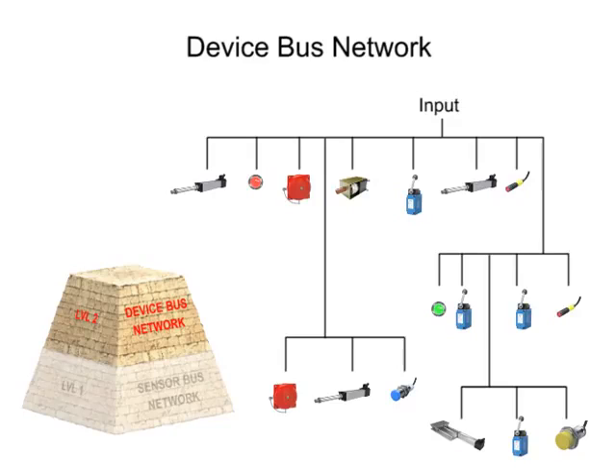The next increasingly complex level of industrial fieldbus networking is the devicebus network. The devicebus network is similar in function to the sensorbus network, but works on a larger scale, connecting many sensors and actuators together. It also connects equipment to variable speed drives and motor control centers that allow for control of individual elements in the network.